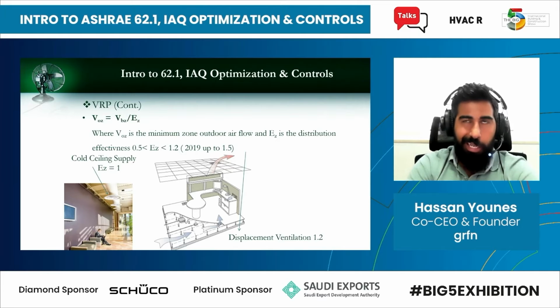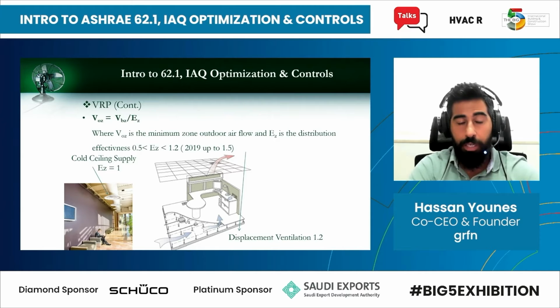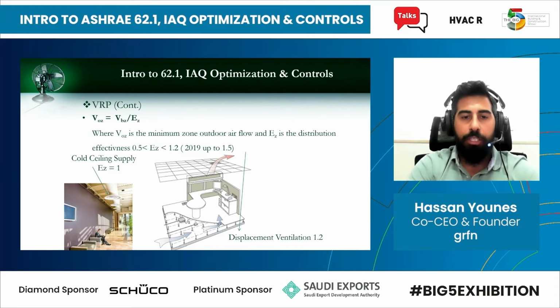Otherwise, let's say, hot ceiling supply would result in 0.8 distribution effectiveness, and that will mean that you need to increase the amount of outside air because of that. So if you are in a cold climate and you're supplying hot air that is 8 degrees C more than the space temperature, then you'll end up with extra required outside air, because most of that air will be stuck to the ceiling. Hot air is at lower density, so from the buoyancy effect some of it will stick to the ceiling and will not reach the occupants, and this is why you're penalized and you need to supply more outside air.